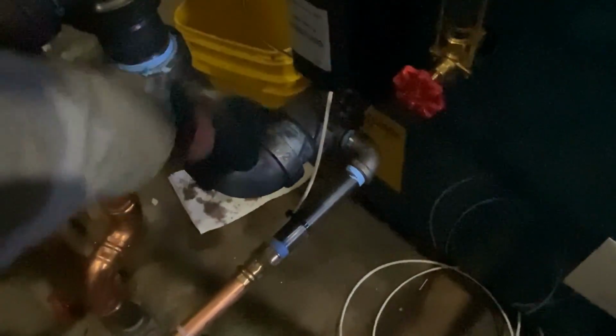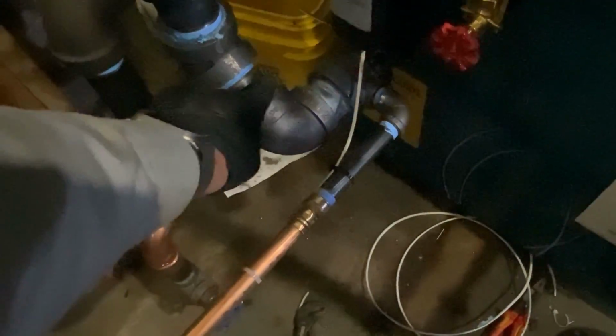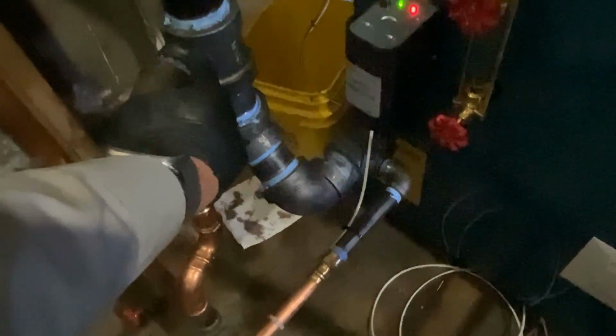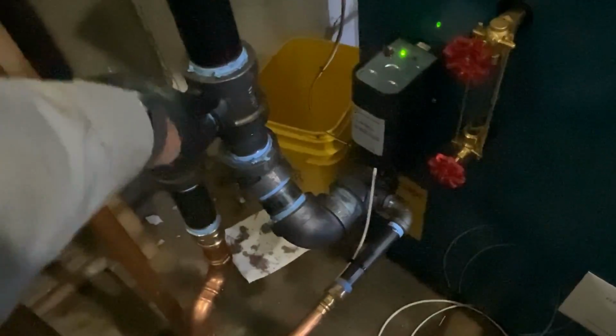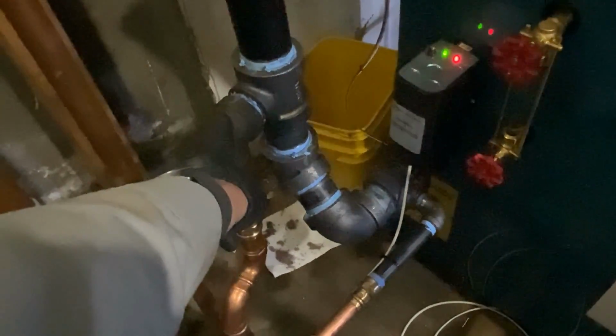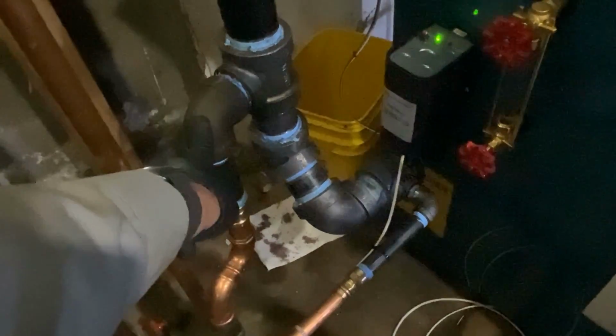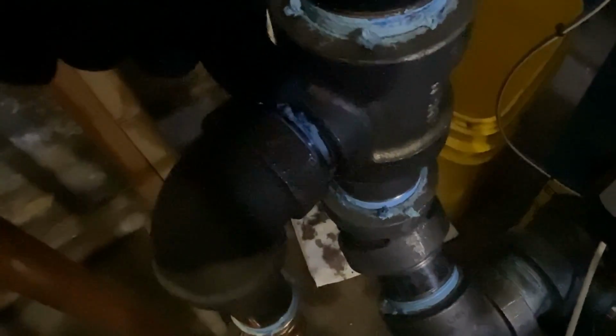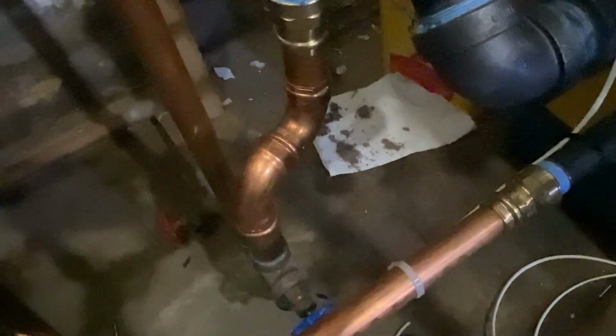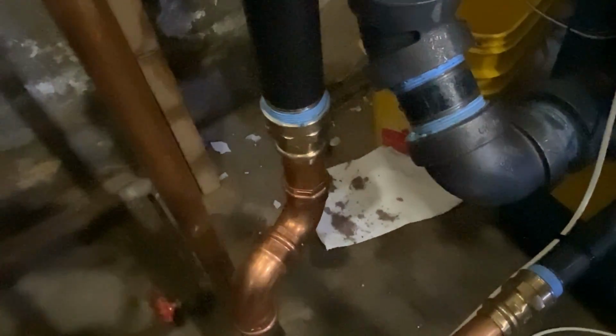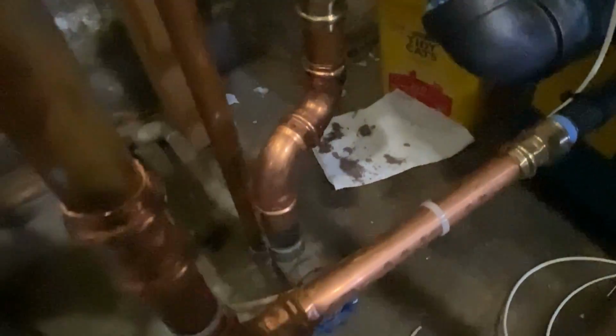Another nipple, 2-inch, steam 90, another nipple, a steam 45, another nipple. This is our Hartford loop T, 2 by 1.25 inch. Out of that 1.25 inch side, we got a 1.25 inch close nipple, and then another Viega dielectric. I'm using it as a dielectric female adapter to pick up our copper wet return. At the top of the Hartford loop T, a long nipple, and then we'll talk about our fittings.